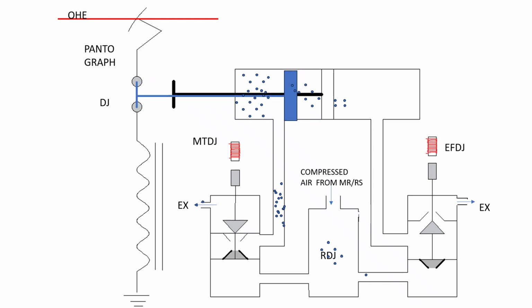Friends, this is PowerPoint animation, and it is better as a teaching aid. But accurate animation is expensive, and that budget is difficult to bear without a very big institution. But at home I am doing this. I have tried to tell you the operation. The Mtdj first energized, and the air pressure in the left side of the chamber is released. Then Efdj energized. Then it will allow the air pressure to the right chamber and press the piston to close the DJ circuit breaker, and the 25 kV energizes the main transformer. This is the basic idea.